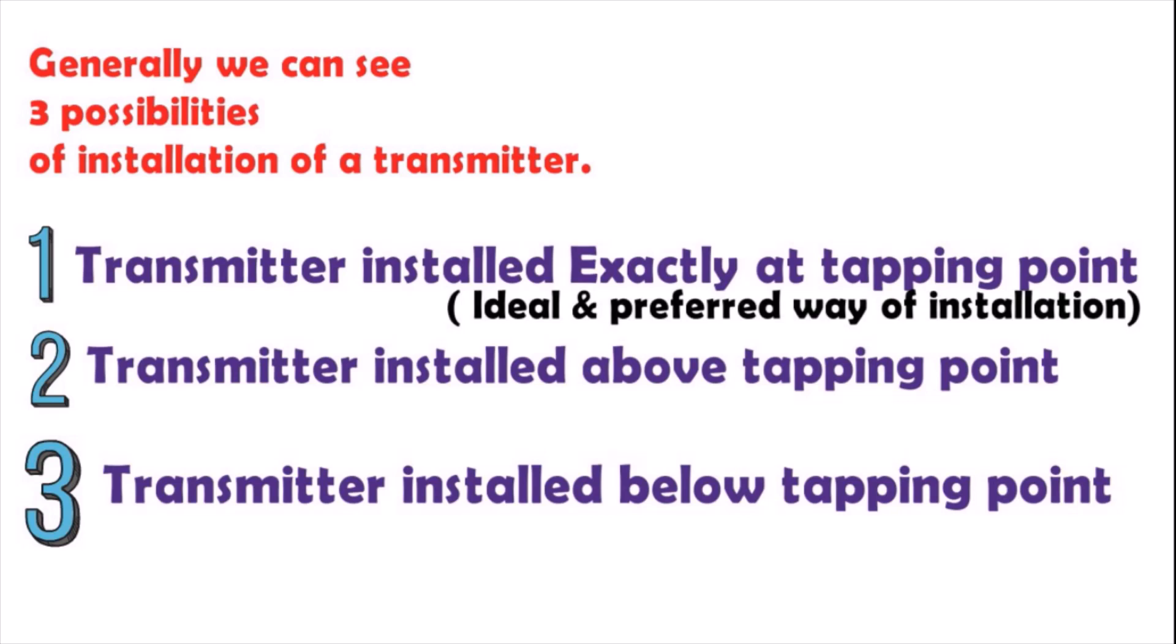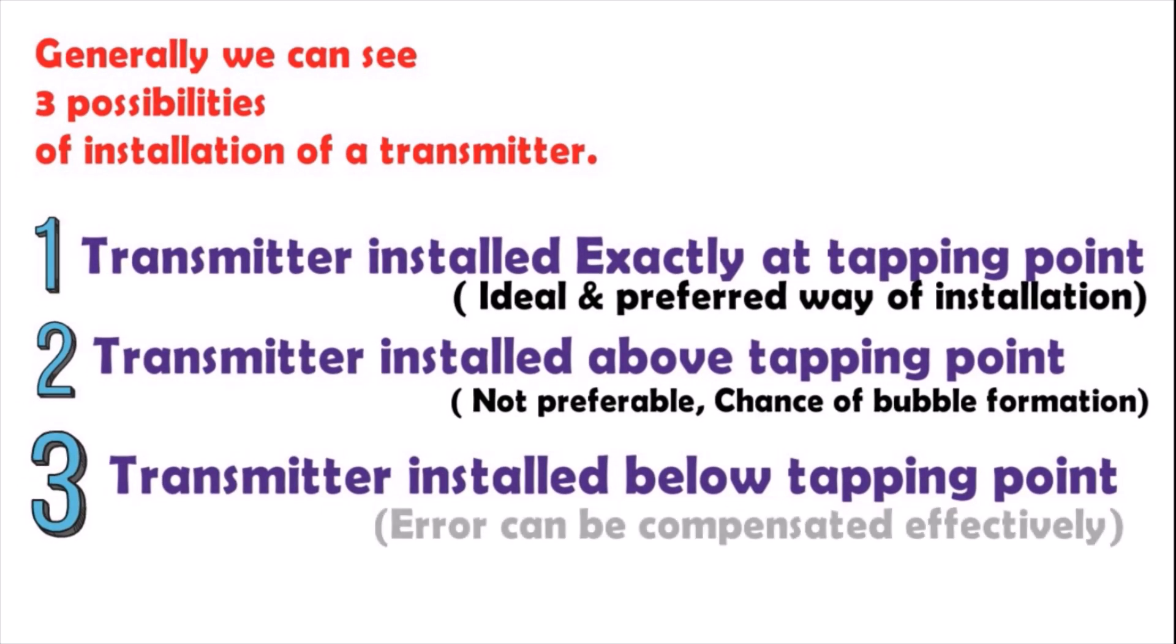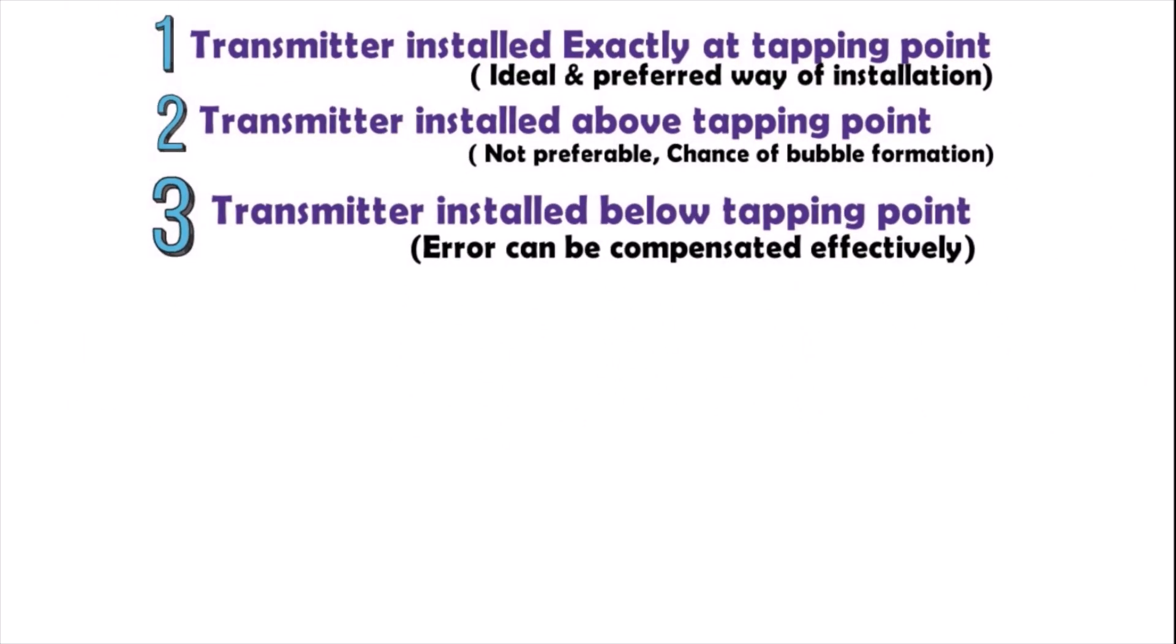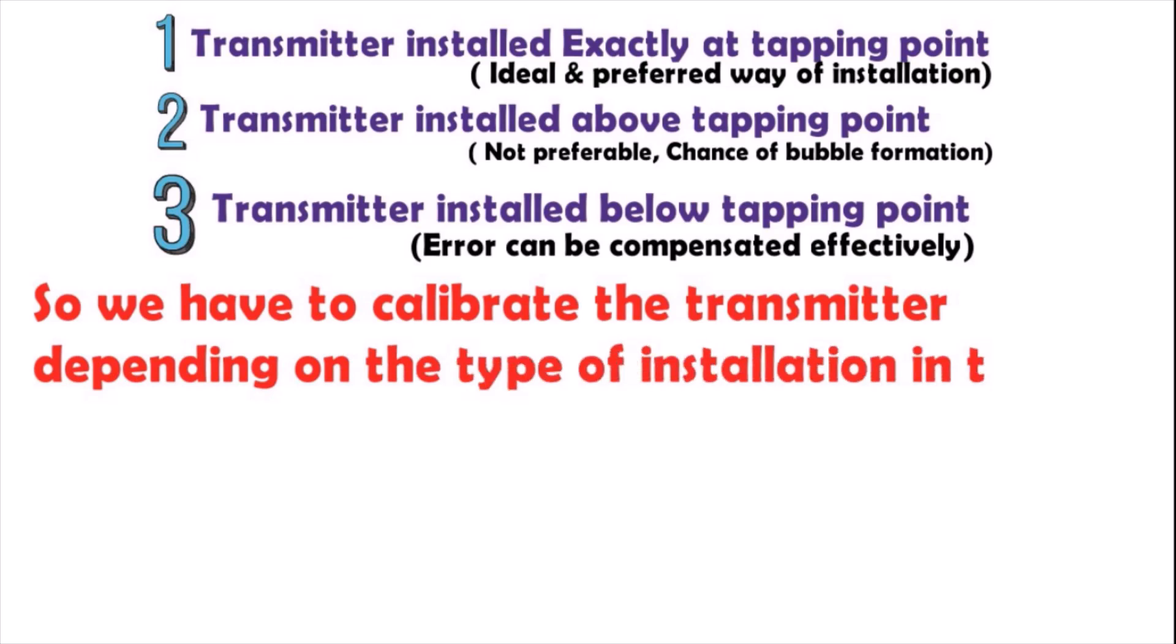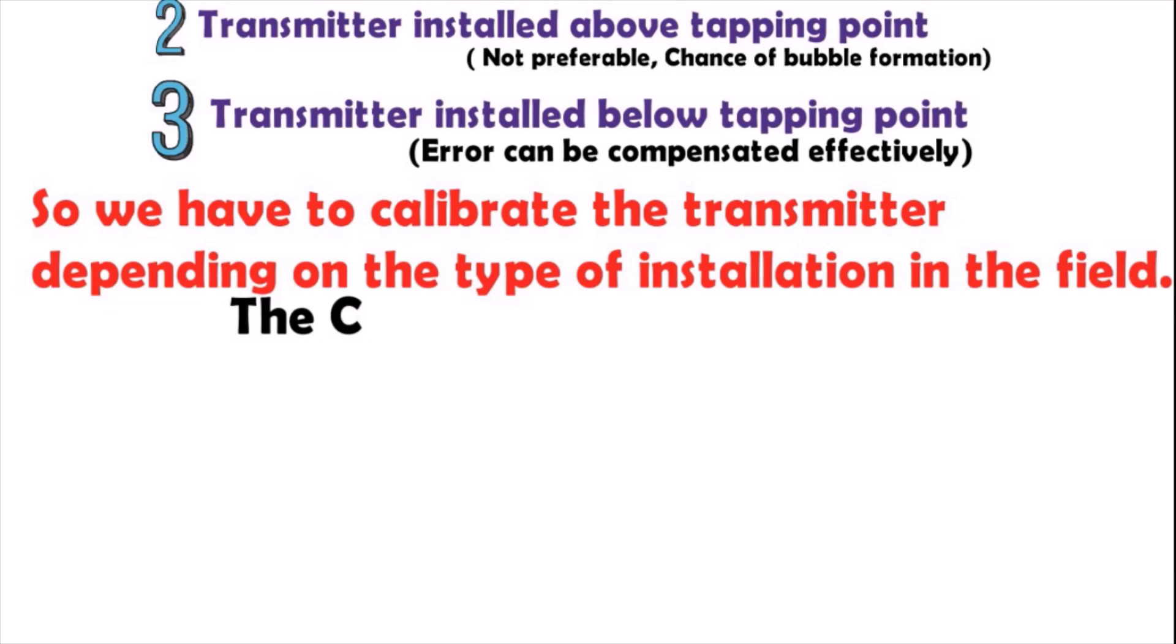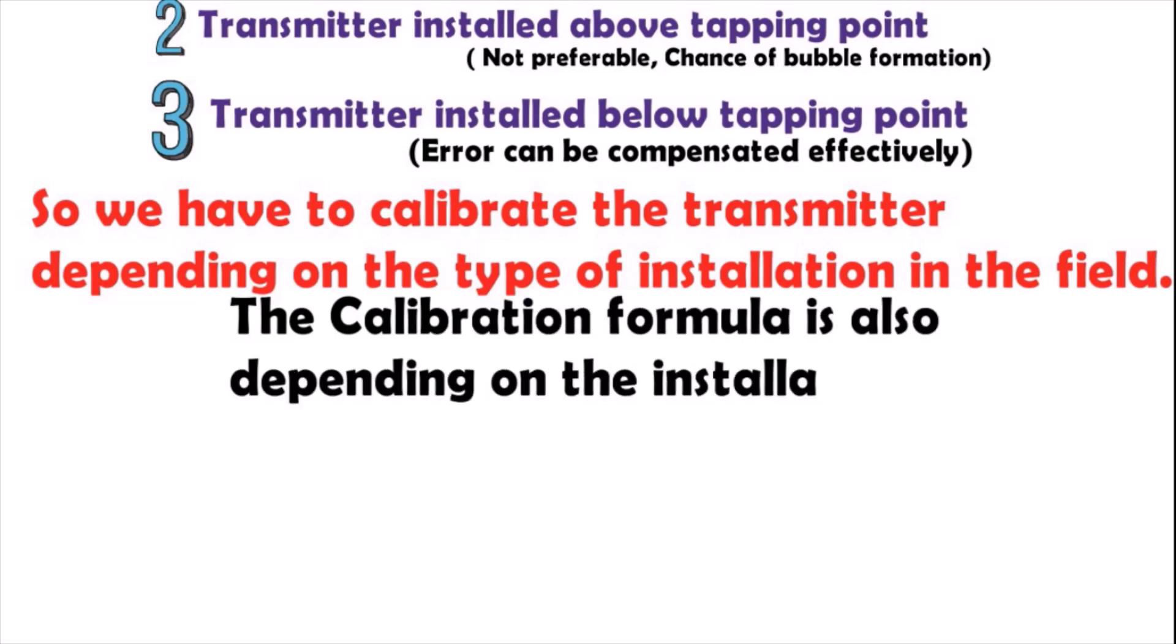The first case is the ideal and preferred way of installation. The second is not preferable due to chance of bubble formation. And the third one, error can be compensated effectively. So we have to calibrate the transmitter depending on the type of installation in the field. The calibration formula also depends on the installation.